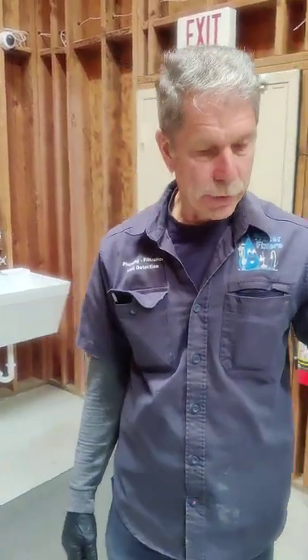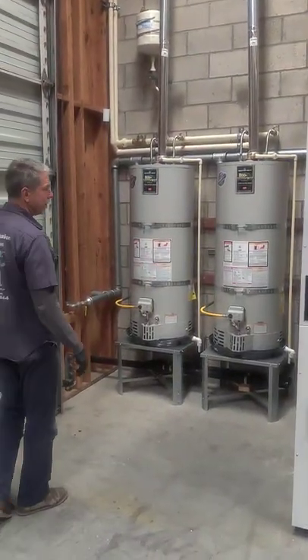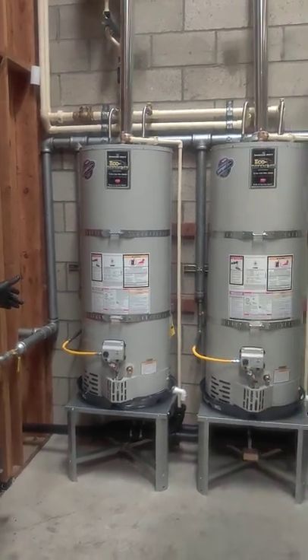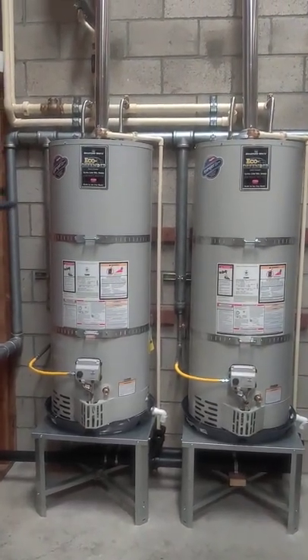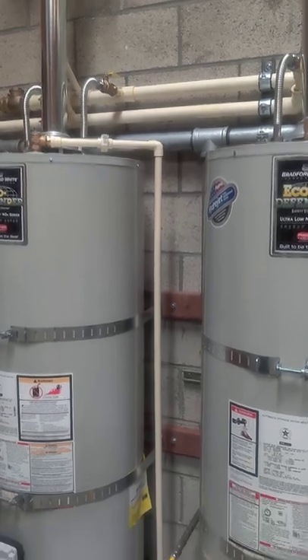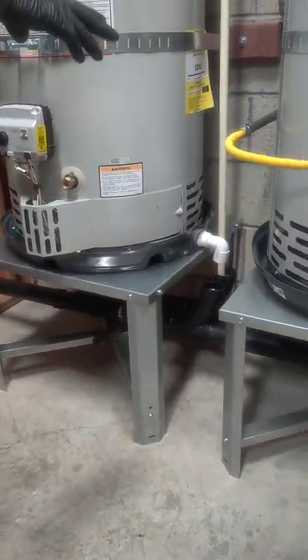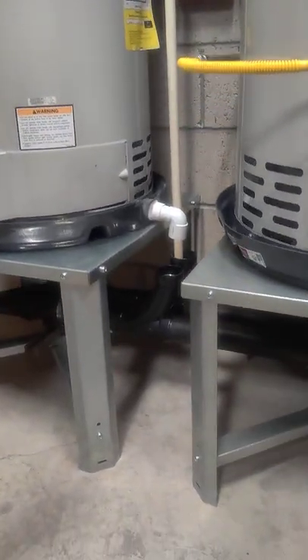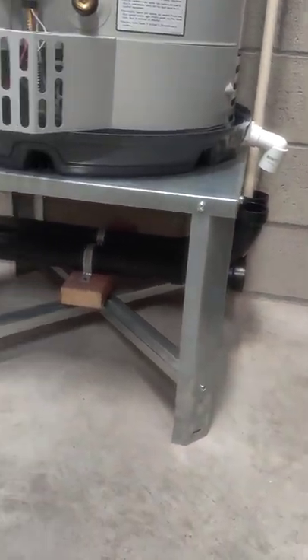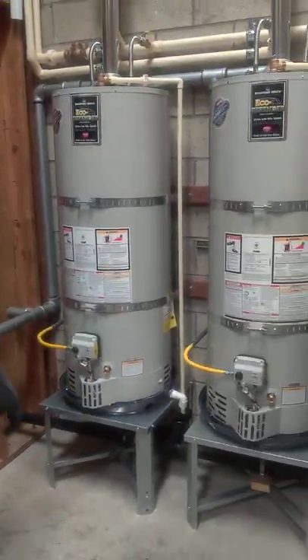Back over to our water heaters and dryers — we staged all the dryers according to the manufacturer's specification and installation manuals. The water heaters are set up on stands and are code-compliant based upon earthquake strapping and the temperature and pressure relief valve overflow lines. We fabricated a special drain assembly to handle the exhaust drains — if there's ever an overflow in the water heater pans, that water drains into traps built from two-inch ABS piping that runs outside the building.